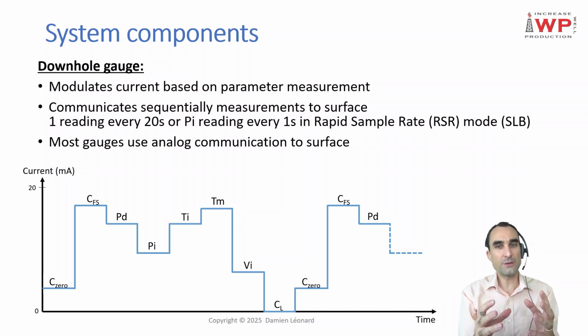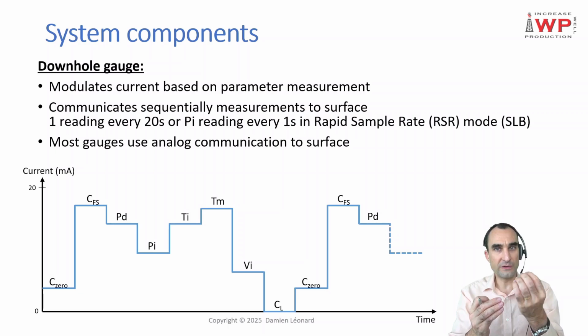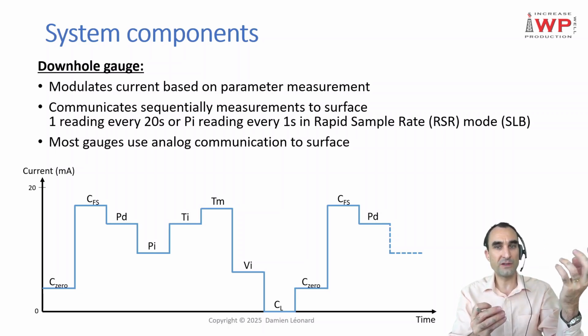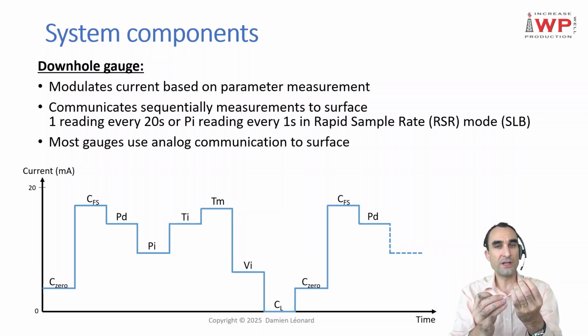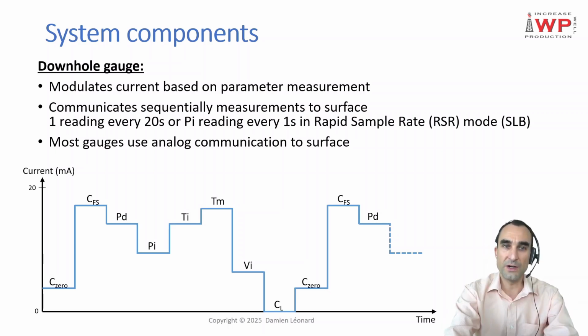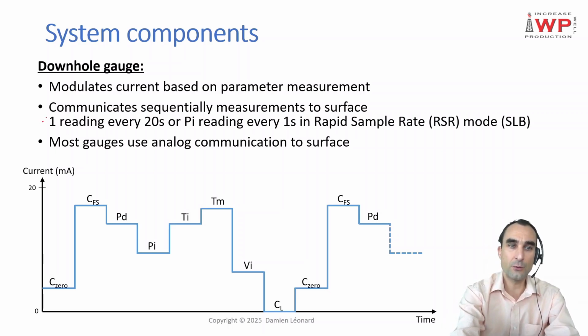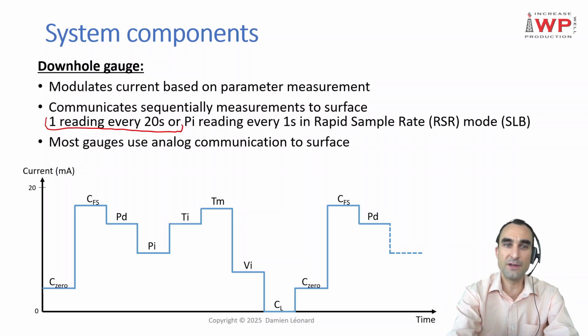Your gauge connects the power sent from the surface to the first sensor, for instance the pump intake pressure, and allows this sensor to communicate with your surface panel. Then it changes the connection and connects the power to the next sensor, for instance the pump discharge pressure, allows it to communicate with the surface panel, and then moves on to the next sensor. So it allows this sequential communication. Now, what is the consequence of that? The consequence is that you're going to have one reading every several seconds.